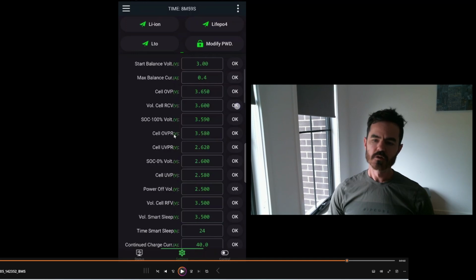Okay, cell over voltage protection return, 3.58. That means if at any point we trigger the over voltage protection at 3.65 volts, it won't allow charging the battery again until the voltage goes under 3.58 volts. I'm okay with that, I'll leave that.